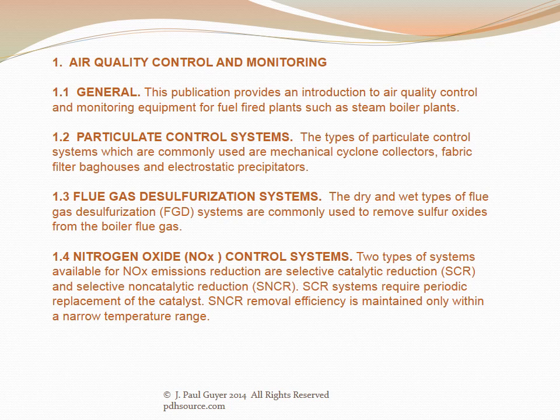Nitrogen oxide, abbreviated NOx, NOx control systems. Two types of systems available for NOx emissions reduction are selective catalytic reduction, abbreviated SCR, and selective non-catalytic reduction, abbreviated SNCR. SCR systems require a periodic replacement of the catalyst. SNCR removal efficiency is maintained only within a narrow temperature range.